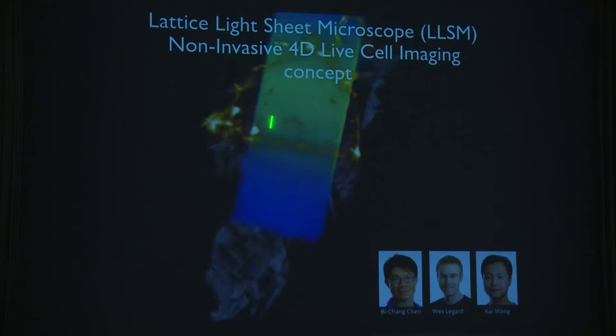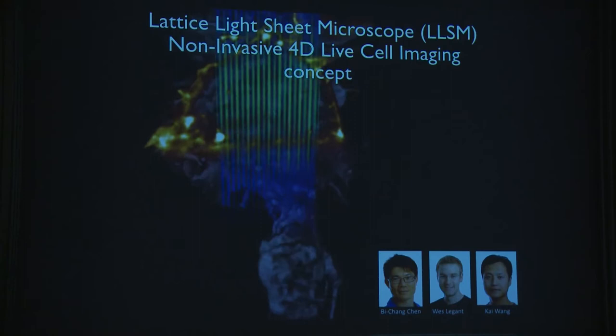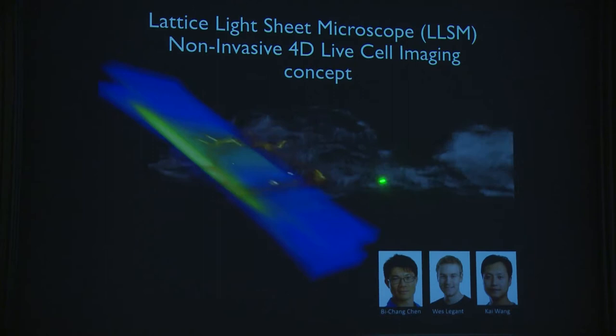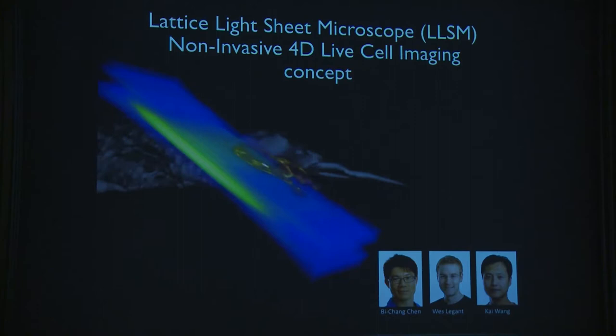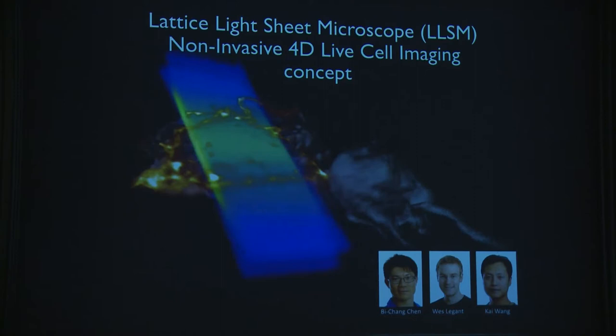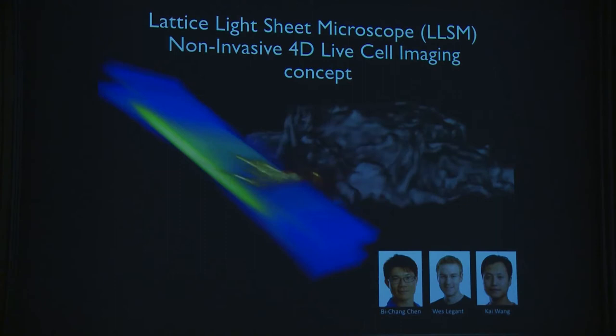In practice: you have the lattice, you dither it with a galvo mirror, and move the sample against the optical axis. You can also move the beam and objective while keeping the sample stationary. The fastest we've run is 3–5 milliseconds per plane; normally 20 milliseconds per plane to avoid bleaching GFP or similar fluorophores. The light dose is low enough not to damage cells — you can even image cell division without inducing DNA damage.